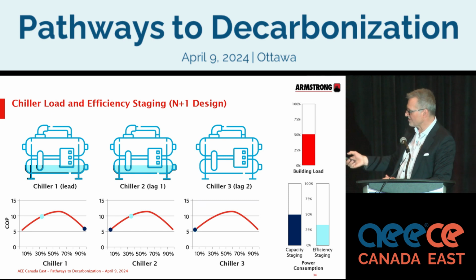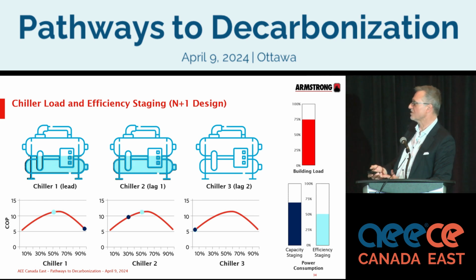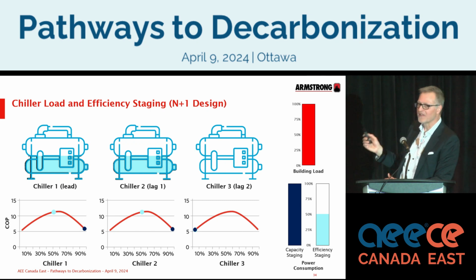If we do the efficiency-based staging, we're actually splitting the load. And you'll see now the COP is actually higher. If the load increases, the second chiller stages on, whereas we are still splitting the load between the two. And then if it goes to 100%, the second chiller goes to 100%, but now, and this is especially true in a lot of N+1 applications, what the logic does is if I have a redundant piece of asset there, I'll bring that piece of equipment on. And now I'm splitting that load between 3 units as opposed to 2.